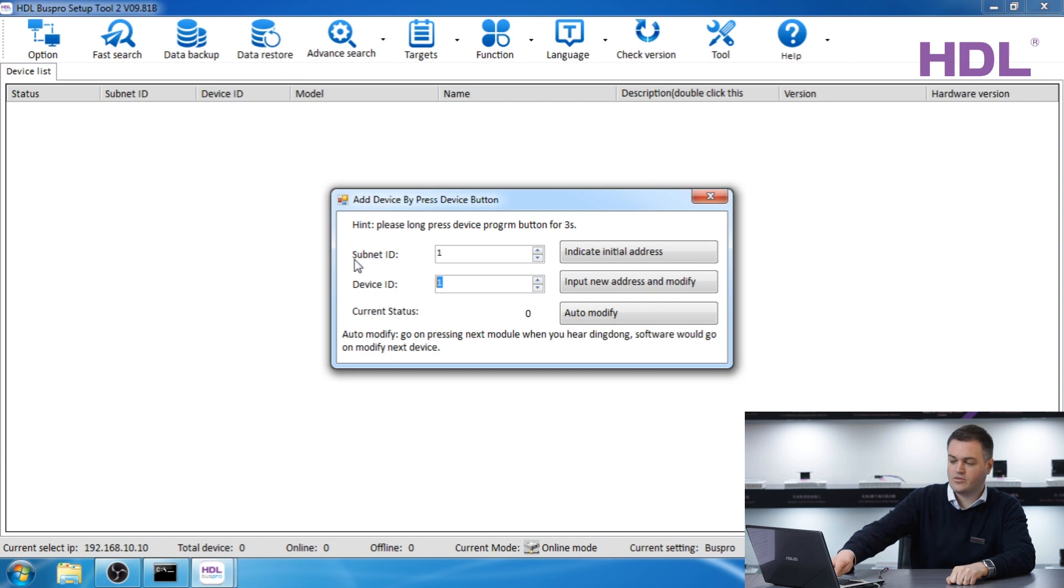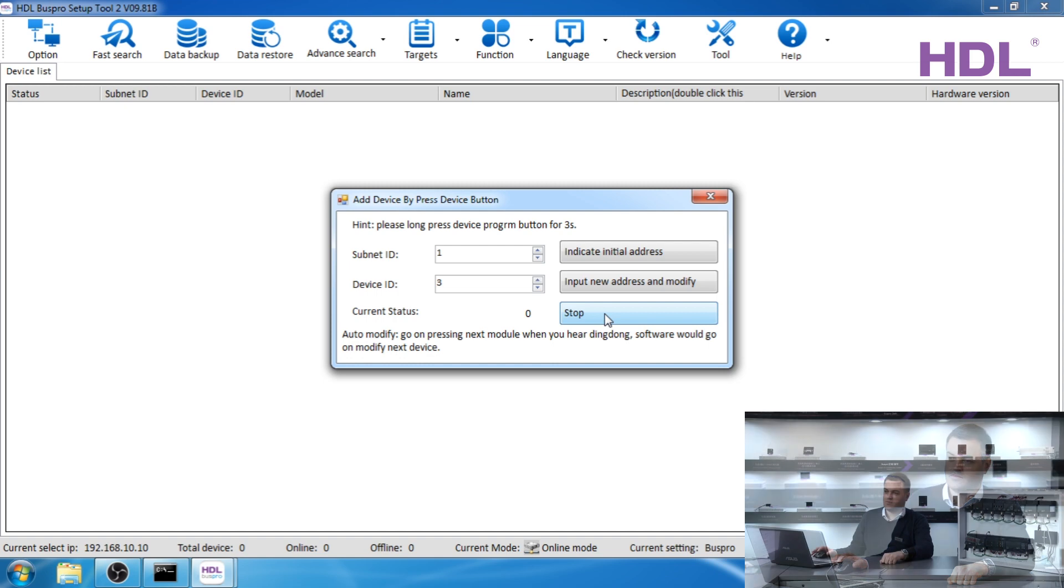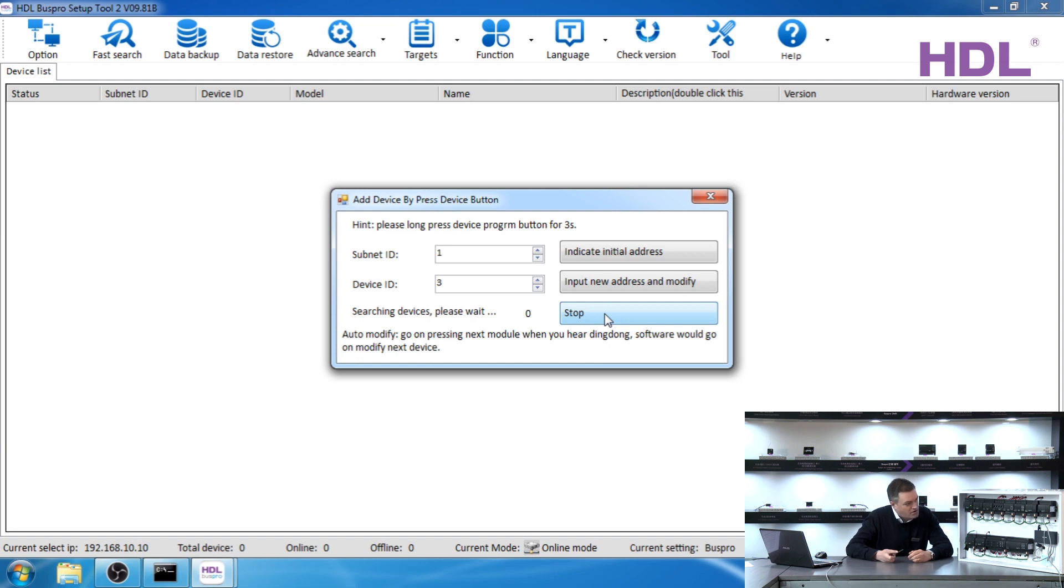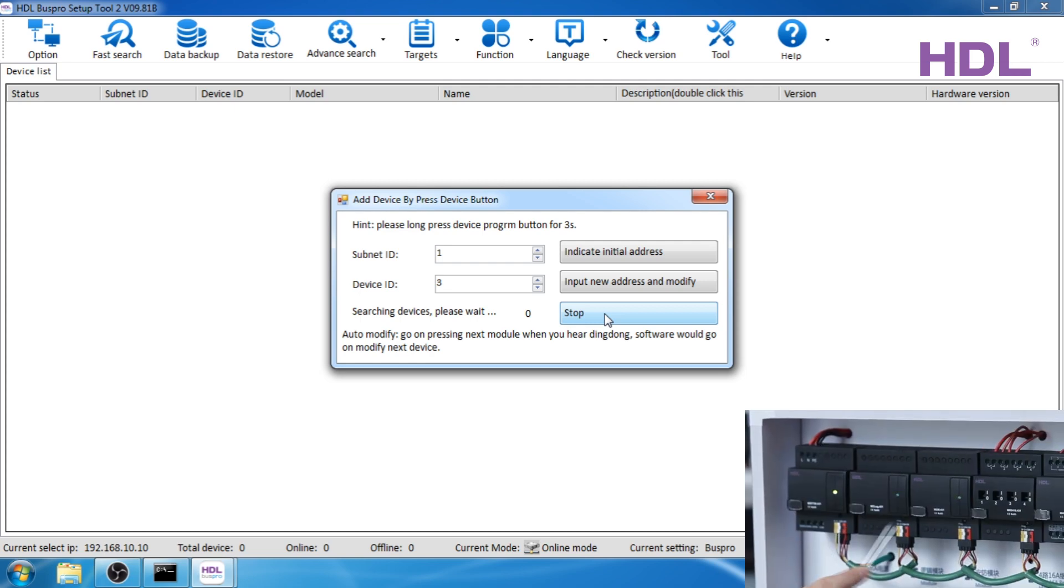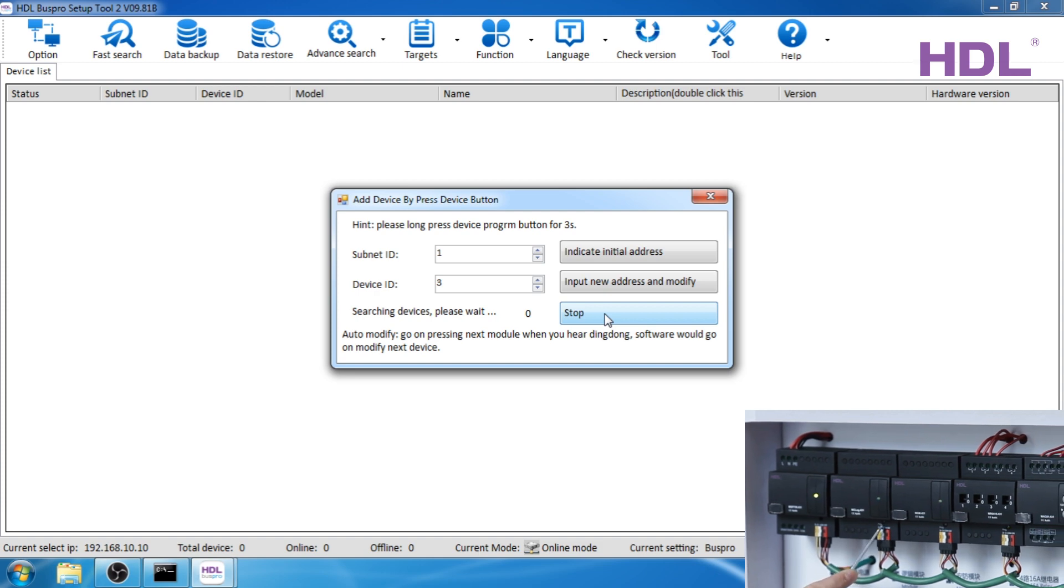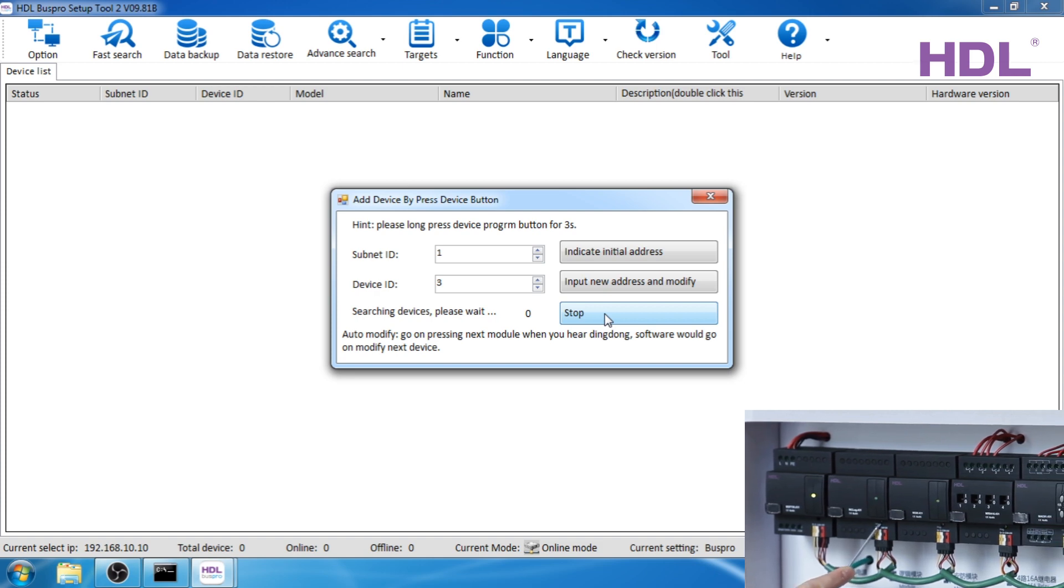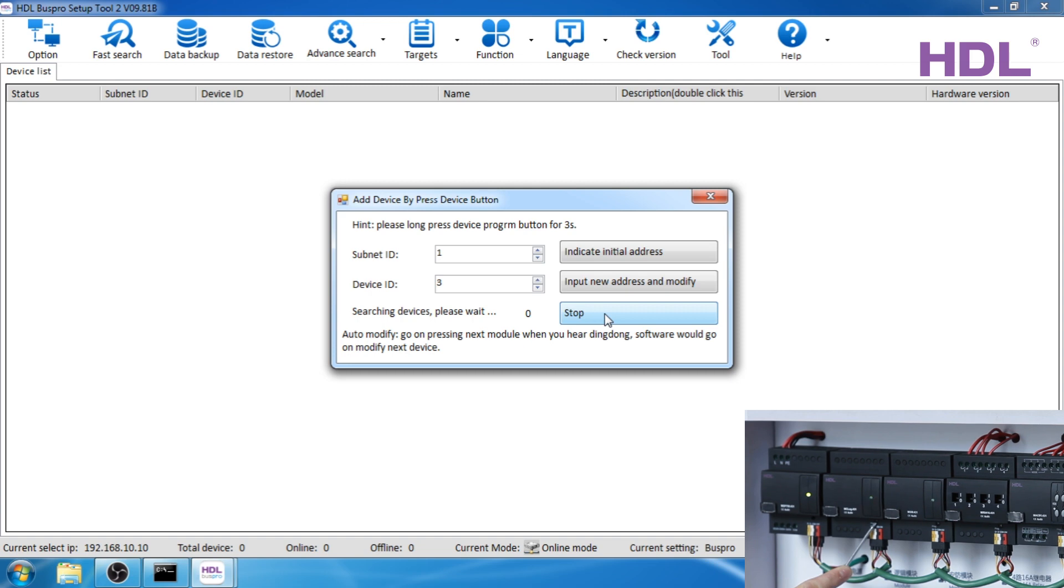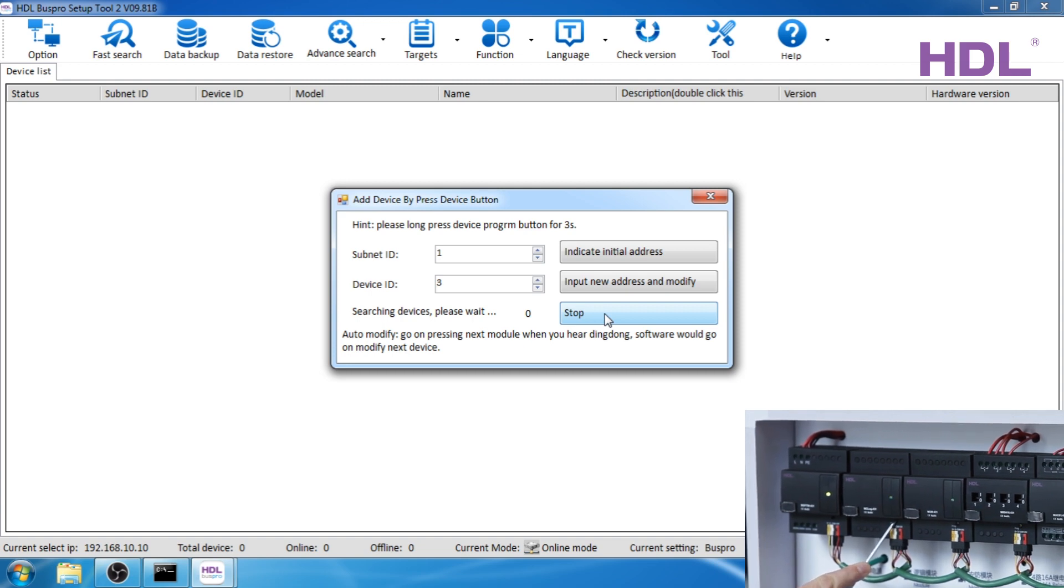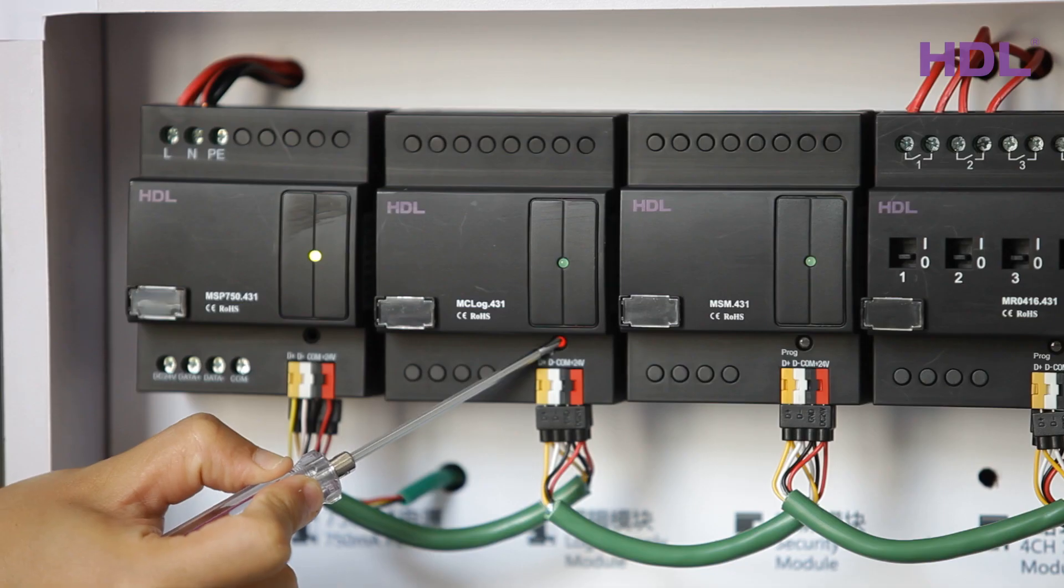In this window we can use something called auto modify. Because we have already done one and two, we're going to start with three and we're going to press the button auto modify. The system is now waiting for us to press each device. I will start with the first one, this one, this one to the left does not have an address because it is a power supply. The next one is the logic module so we need to locate the small green button and press and hold for three seconds.